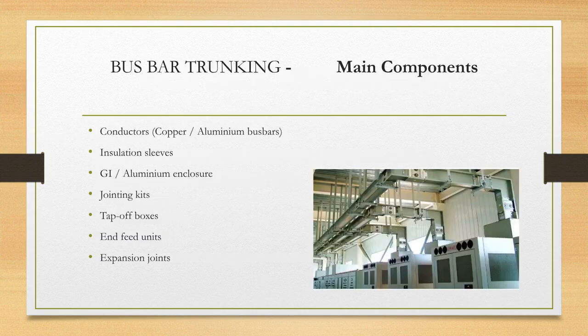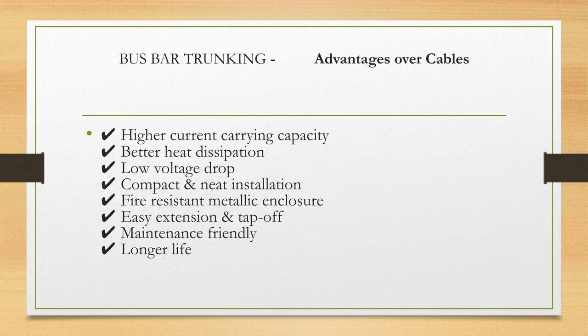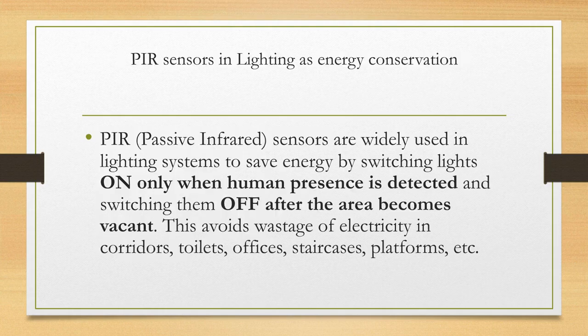Main components of a busbar trunking system include copper or aluminum conductors, insulation sleeves, GI or aluminum enclosures, jointing kits, tap-off boxes, end feed units, and expansion joints. Busbar trunking offers several advantages over cables, such as higher current carrying capacity, better heat dissipation, low voltage drop, compact installation, and a fire-resistant metallic enclosure. They are also easy to extend and maintain and have a longer life.